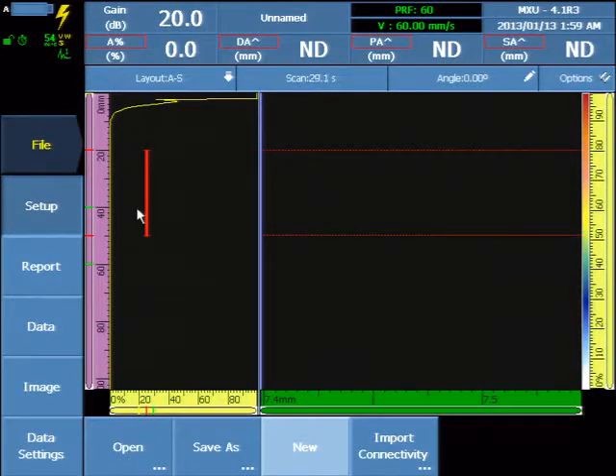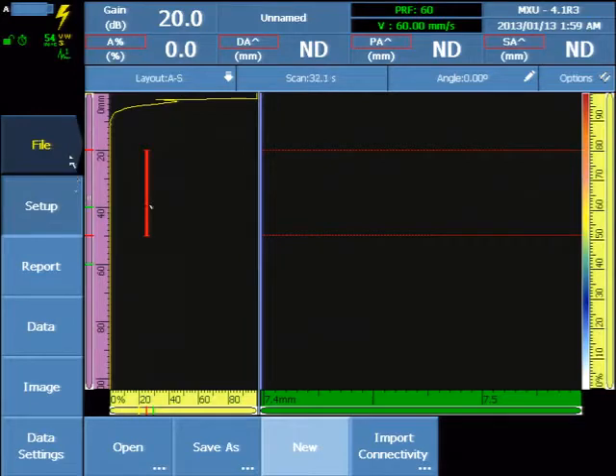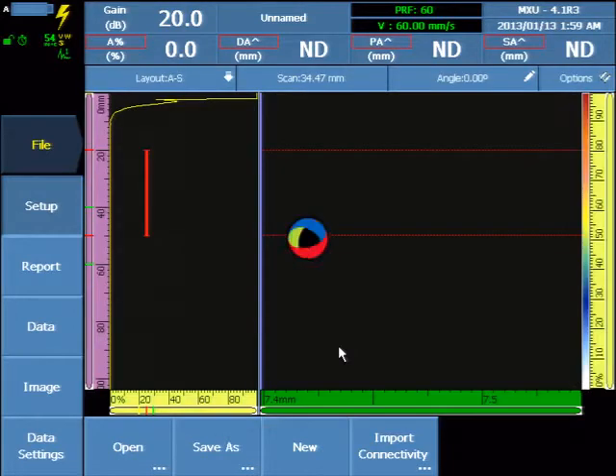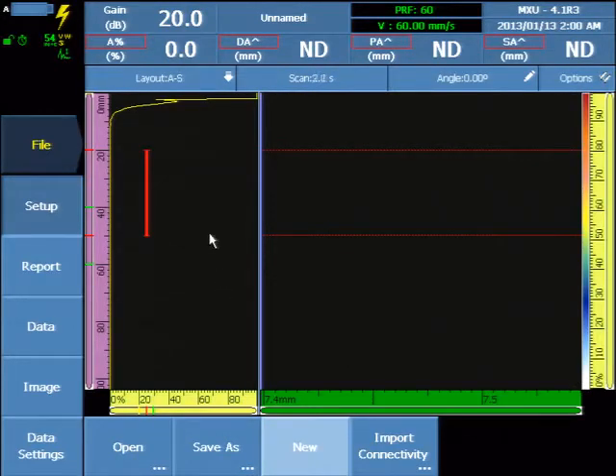Configuration of the OmniScan SX for single group TOFD starts with the File menu and select New. This clears out any existing configuration and loads a default A-scan.